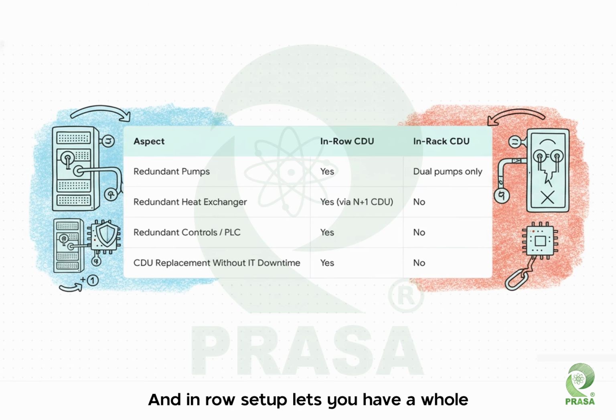An in-row setup lets you have a whole extra CDU on standby. That's what we call N+1 redundancy. So you get backup pumps, a backup heat exchanger, backup controls, the whole shebang. The in-rack unit, yeah, it's got two pumps, but that's it. Everything else is a single point of failure, just waiting to ruin your day.